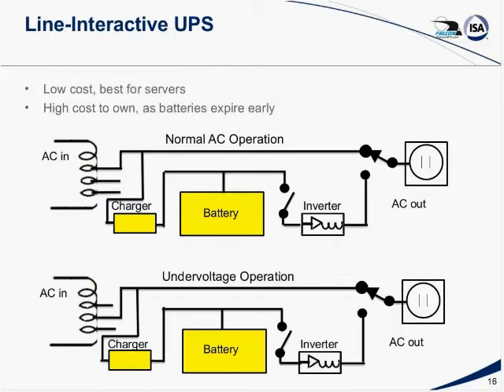A line interactive UPS is good for servers. It actually has taps on the AC in transformer, and it automatically, or smartly if you will, adjusts these taps to maintain the input voltage within a fair range. It generally can operate plus or minus about 10% of the nominal range and hold the AC power in there. But again, when you lose power entirely, it switches into its offline or undervoltage condition in which the inverter works. And it offers no protection other than blackouts and limited transient protection.